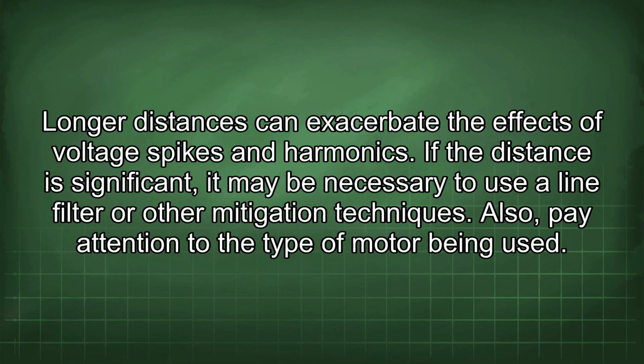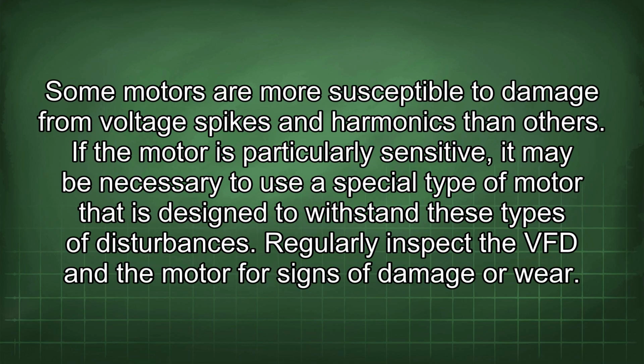Longer distances can exacerbate the effects of voltage spikes and harmonics. If the distance is significant, it may be necessary to use a line filter or other mitigation techniques. Also, pay attention to the type of motor being used. Some motors are more susceptible to damage from voltage spikes and harmonics than others. If the motor is particularly sensitive, it may be necessary to use a special type of motor that is designed to withstand these types of disturbances.